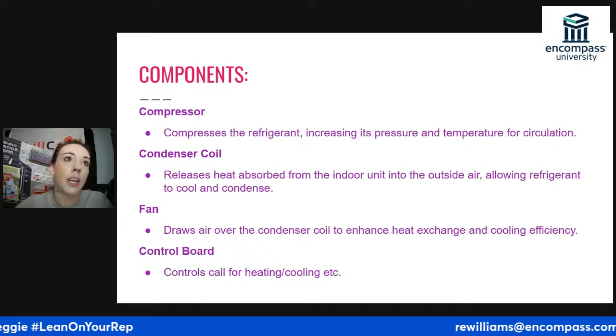So a note from acservicetech.com, how mini split charge differs from conventional split charge. Most current mini split systems are VRF. For those of you who don't know, VRF is variable refrigerant flow. That means that the refrigerant flow changes depending on what the needs are of the load in the home. These systems include an EEV, electronic expansion valve. Most of us are used to seeing a TXV as a metering device. Those are what we see in conventional splits that are 410A, and most R22 as well. But in a mini split situation, you'll have an EEV.